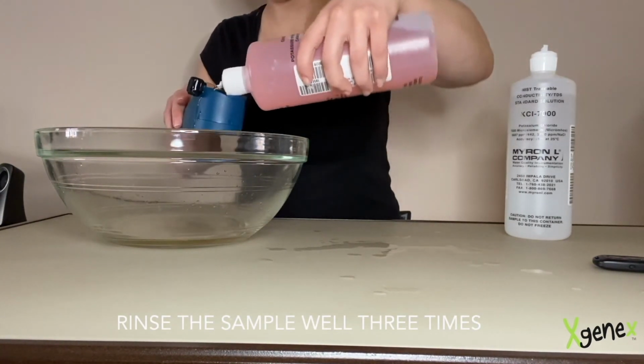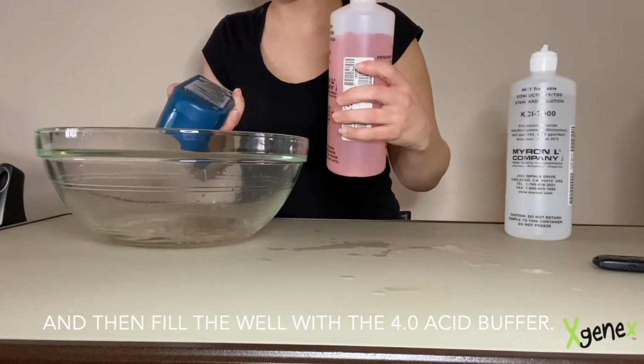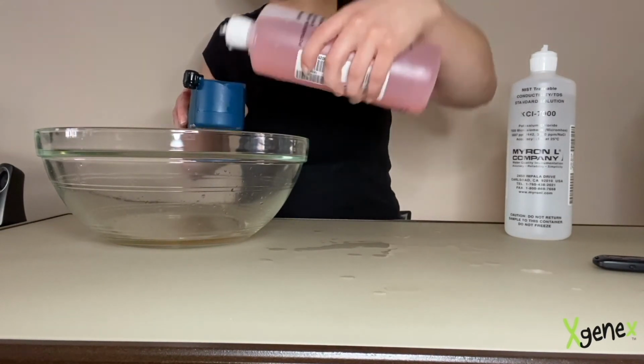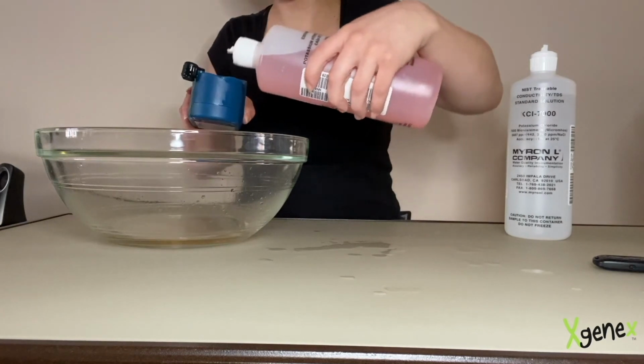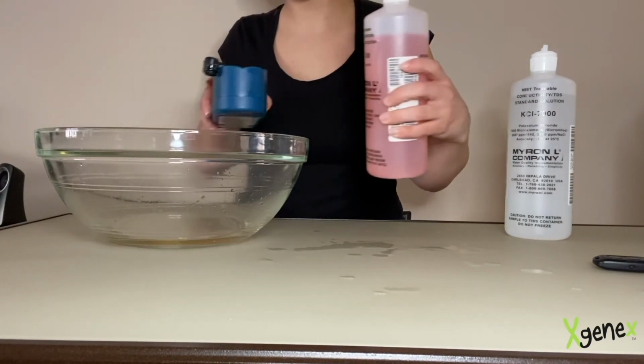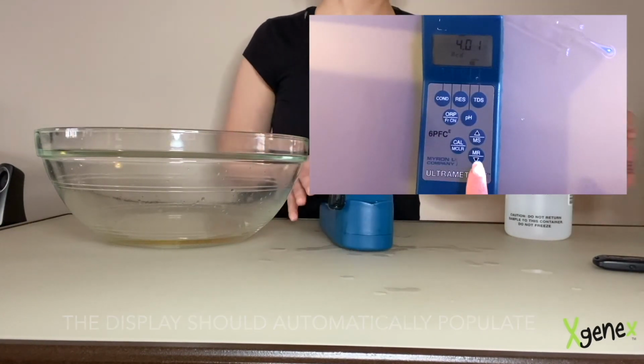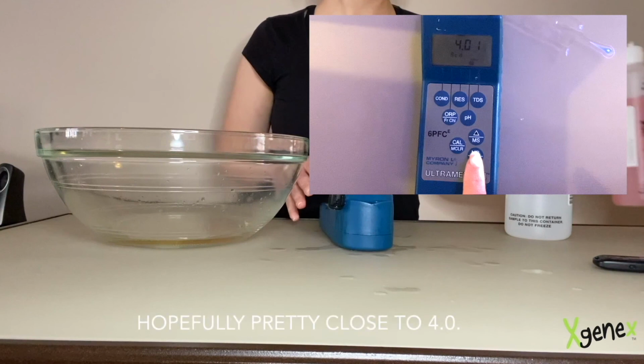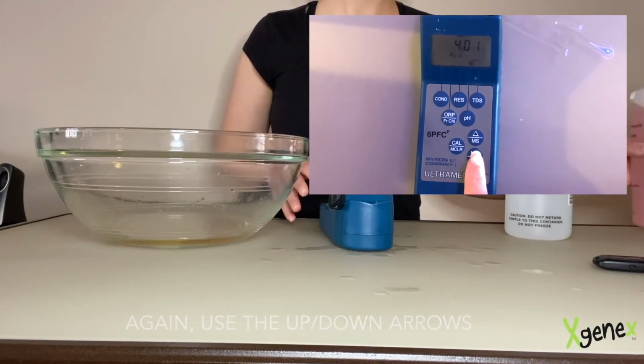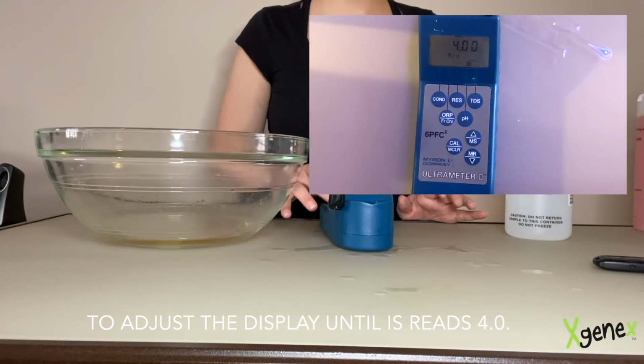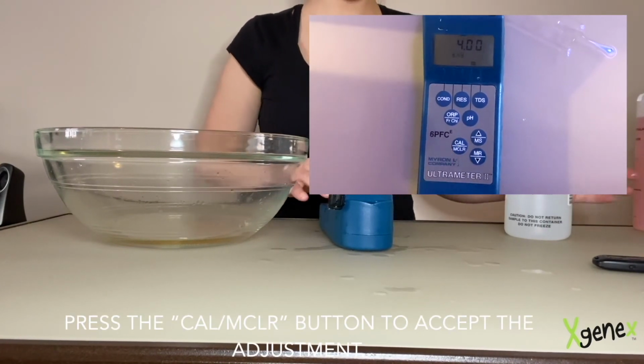Rinse the sample well 3 times and then fill the well with the 4.0 acid buffer. The display should automatically populate with some different numbers, hopefully pretty close to 4.0. Again, use the up-down arrows to adjust the display until it reads 4.0. Press the Cal button to accept the adjustment.